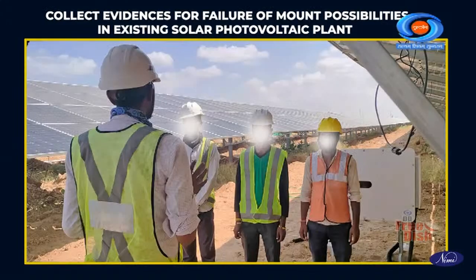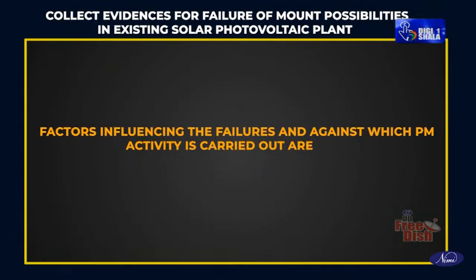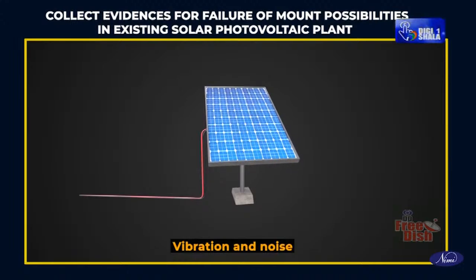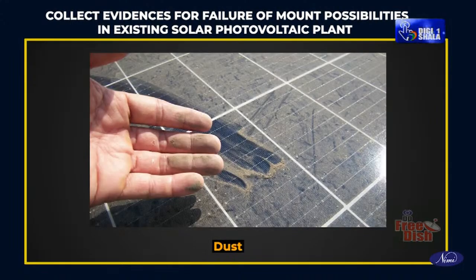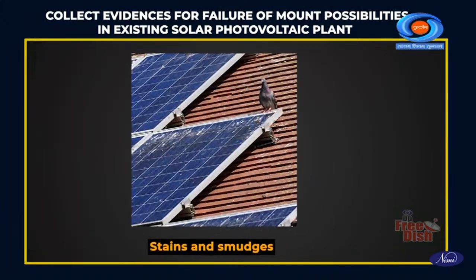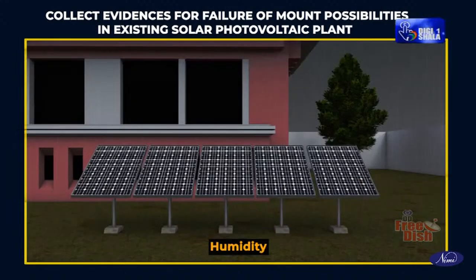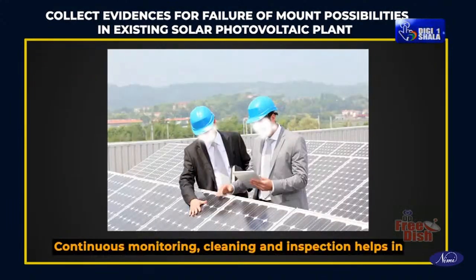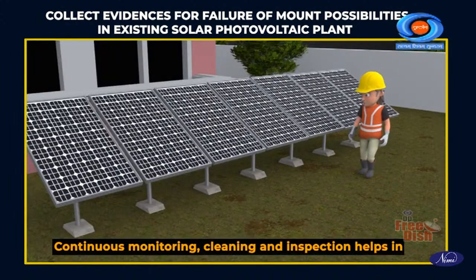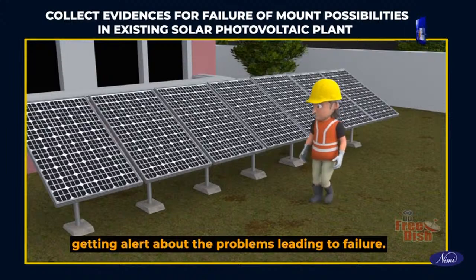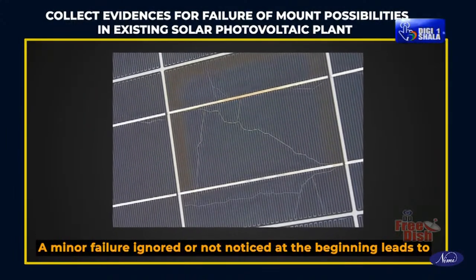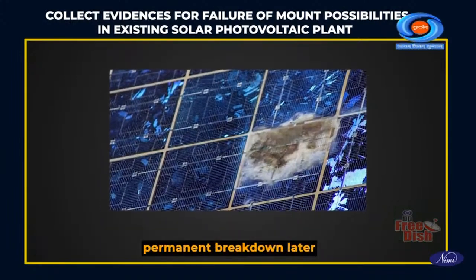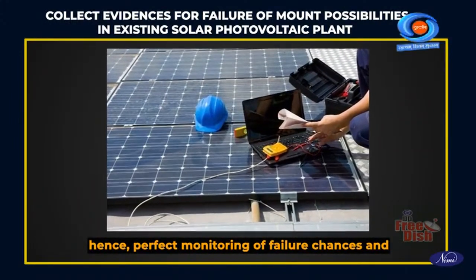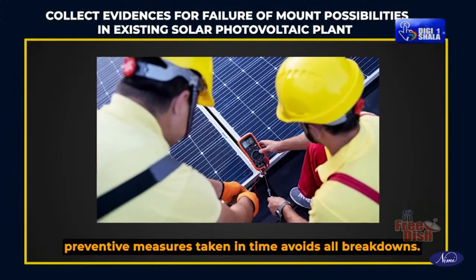Collect evidence for failure of mount possibilities in an existing solar photovoltaic plant. Factors influencing the failures, against which PM activities are carried out, are vibration and noise, shock, dust, damage of cover, stains and smudges, temperature, humidity, corrosion. Continuous monitoring, cleaning and inspection help in getting alert about the problems leading to failure. A minor failure ignored or not noticed at the beginning leads to permanent breakdown later. Hence, perfect monitoring of failure chances and preventive measures taken in time avoid all breakdowns.